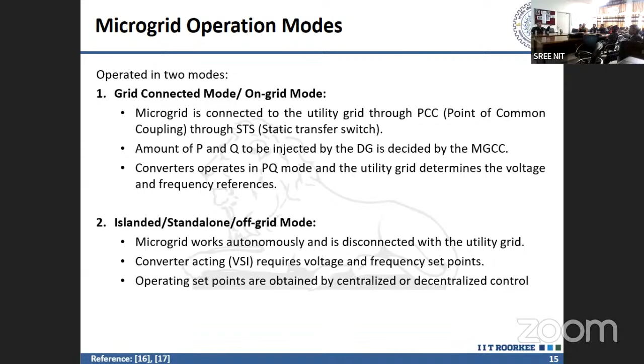Operating set points are obtained by centralized or decentralized control. Because in grid connected mode, all the set points are basically governed by the grid. But in islanded mode, these set points you have to generate: what voltage and frequency you need for your system.